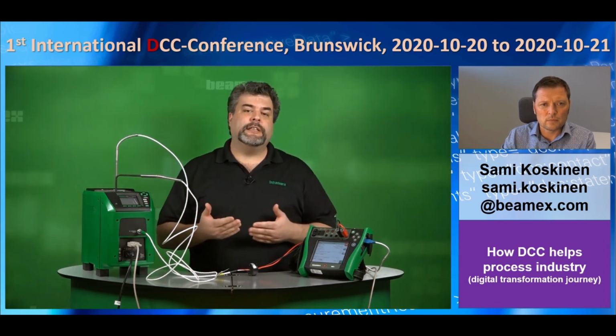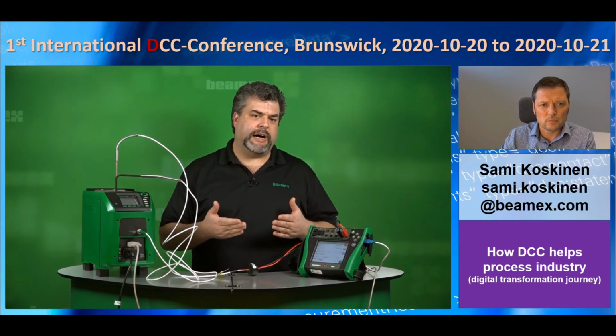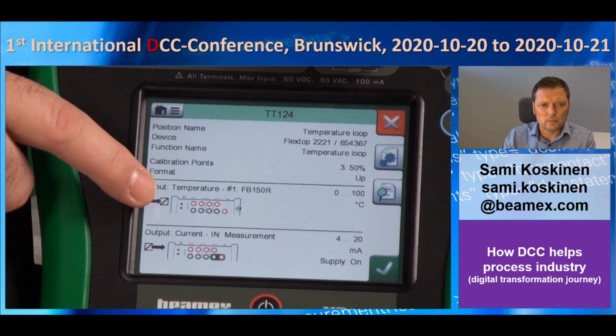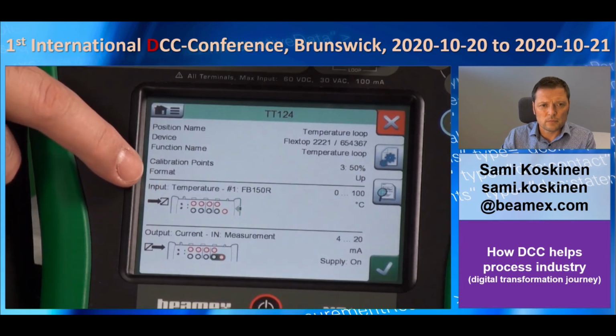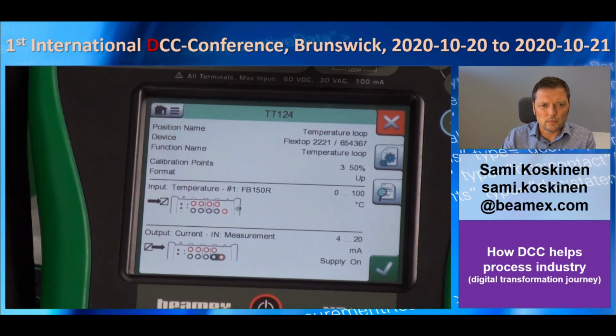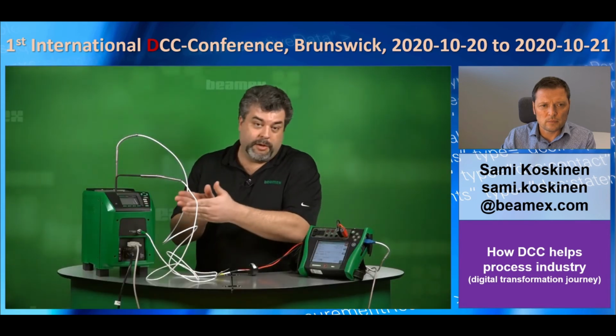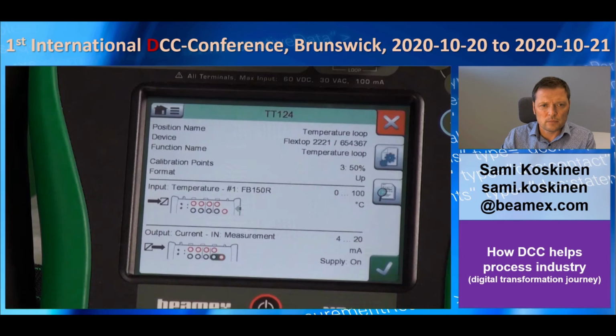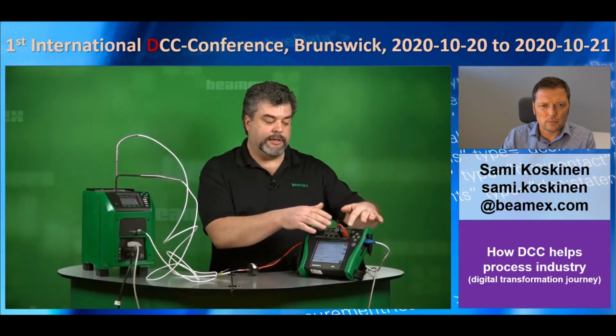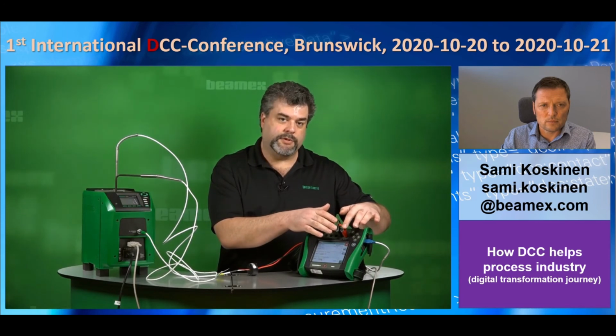Maybe I'm a new technician and I haven't used this a lot. So this tells me for my input, I need to connect my USB. You can see it in green right here. USB cable connecting me over here to my temperature source. And the output of the transmitter is right here. And that tells me to hook up right here. So this will measure the milliamps and provide loop power.